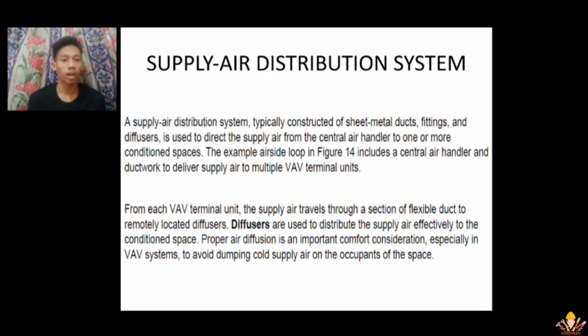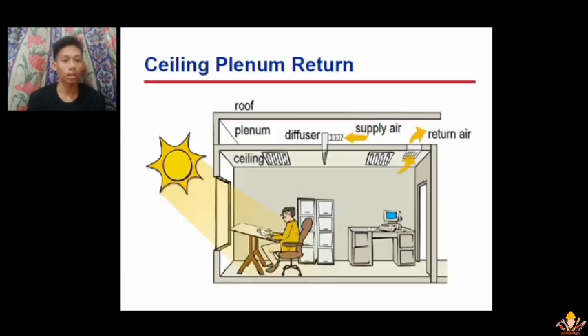The example airside loop in Figure 14 includes a central air handler and ductwork to deliver supply air to multiple VAV terminal units. Diffusers are used to distribute the supply air effectively to the conditioned space. Proper air diffusion is an important comfort consideration, especially in VAV systems, to avoid dumping cold supply air on the occupants of the space. Ceiling plenum return.